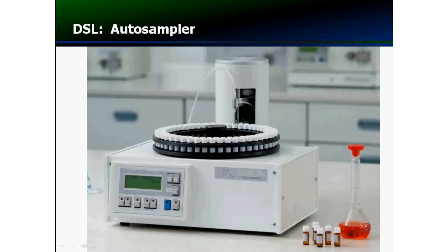The autosampler is a device used in chemistry and biology labs and has two main parts. It has this round part that contains the samples, referred to as the carousel, and this carousel spins around, and inside the carousel are little bottles or test tubes. Back here in the back we see a sampling probe or a sampling needle that moves up and down and moves into the sample vials to either put fluid into the test tube or to pull fluid out.